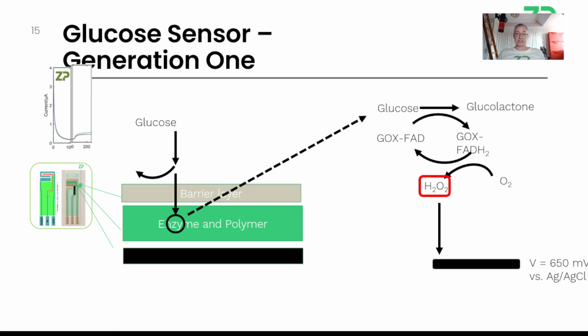We detect it by applying a potential of 650 millivolts positive - be very careful about that. You should get currents in the microamp range because of this flow of electrons, which also recycles the oxygen. But if you're accidentally applying minus 650 millivolts, you're not detecting the generation of hydrogen peroxide - you're detecting the consumption of oxygen instead.